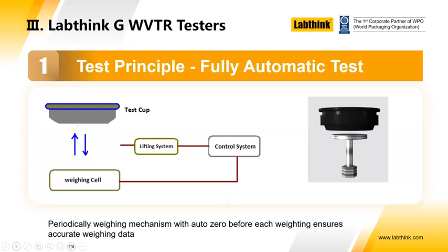One of the biggest issues with performing the test manually is that you have to handle the dishes very carefully. So for example, if we were using a test dish doing the wet method, if any of the contents of the dish splash onto the specimen, that really cancels the whole of the test. And so you might be several days into the test, have already done several weighings and recorded them. Then an accident occurs, somebody splashes some of the contents of the dish onto the specimen, the whole test has to be cancelled and you'd need to start all over again. And so by using an automated system like this, it virtually eliminates the scope for any kind of human error.